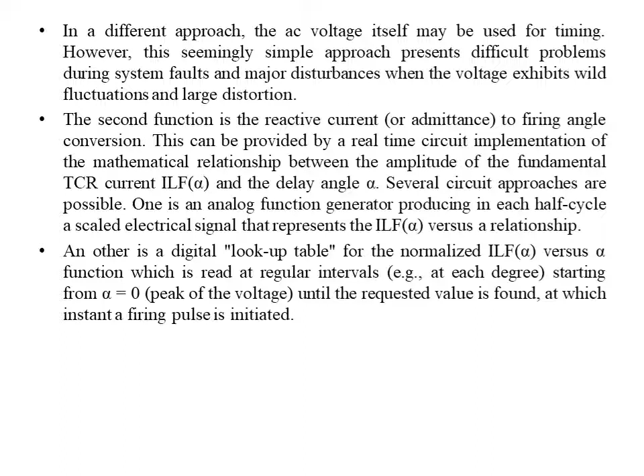Another is a digital lookup table for the normalized ILF alpha. Whatever inductive current is obtained will be converted into a particular firing angle by using a lookup table, as in the case of a microprocessor. If we get the magnitude of current, there will be a stored value of signal or pulses for that particular current, and those pulses will be given to the particular devices. The digital lookup table for normalized ILF alpha versus alpha functions is read at regular intervals, for example each degree starting from alpha equal to 0, until the requested value is found, at which instant a firing pulse is initiated.